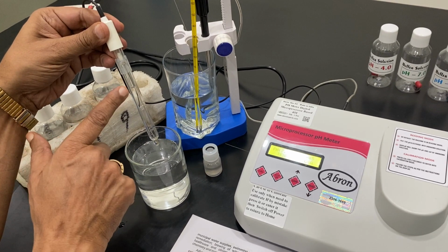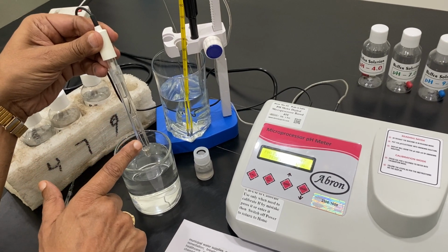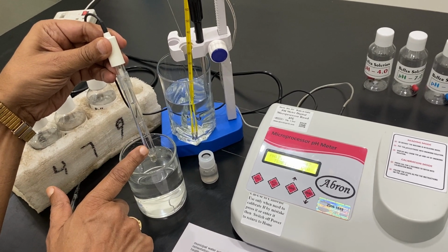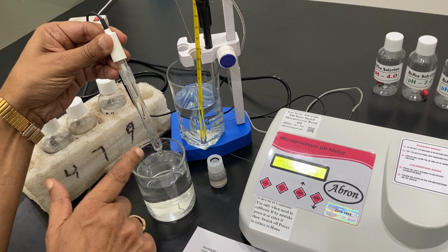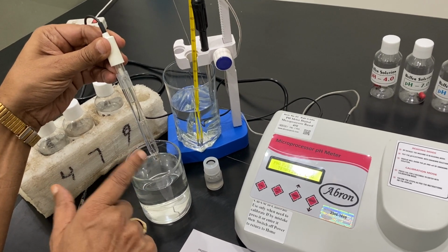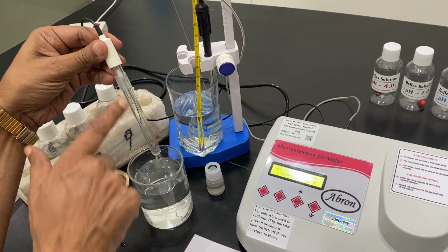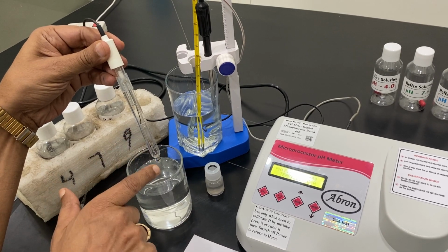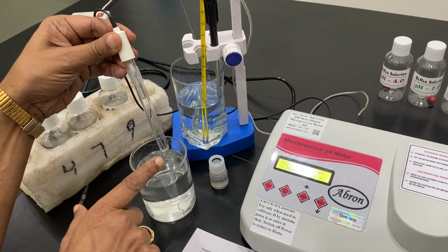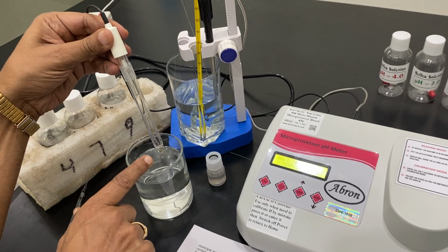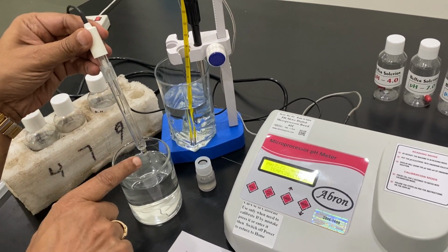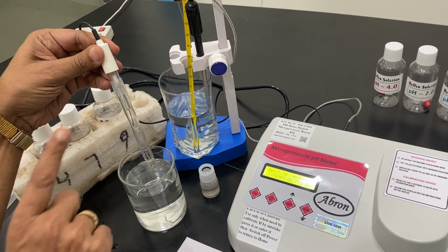The third problem is that the solution is not visible in the electrode cell tube. The reason may be that it is broken. If you put in new solution, it goes out. That means the tip is broken. Then you have to use a new combined electrode. If it is completely filled and the solution is still there, then only it will work.